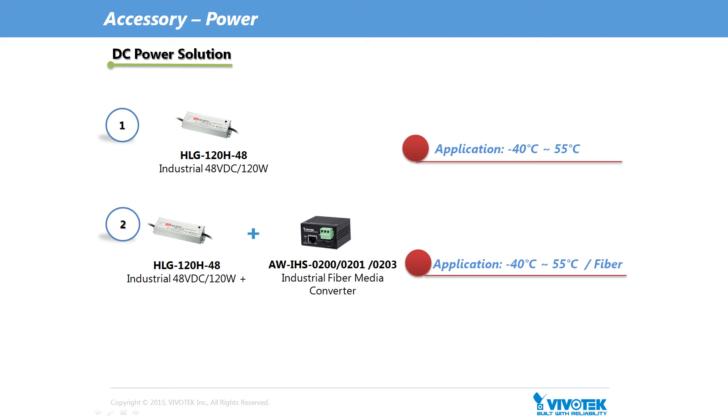Besides support for PoE environments, VIVOTEK also provides two options for local DC power solutions. First, to meet temperature requirements from minus 40 to 55 degrees C, VIVOTEK's industrial 48V DC 120W HLG120H48 can be selected. Second, by selecting VIVOTEK's HLG120H48 industrial 48V DC 120W power supply and VIVOTEK's industrial fibre media converter with model names AWIHS0200, 0201 and 0203, the SD9364 EHL can be deployed in outdoor fibre interface environments.